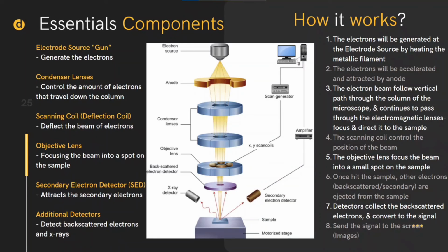So how does this SEM work? First, the electrons are generated at the electron source by heating the metallic filament. Next, the electrons are accelerated and attracted by an anode. And then the electron beam follows a vertical path through the column of the microscope and continues to pass through the electromagnetic lenses, which focus and direct it to the sample. And then the scanning coil controls the position of the beam, and the objective lenses focus the beam into a small spot on the sample. Then, once it hits the sample, other electrons, that is backscattered or secondary electrons, are ejected from the sample. Next, the detectors collect the backscattered electrons and convert them to a signal and send the signal to the screen, which will produce the image.